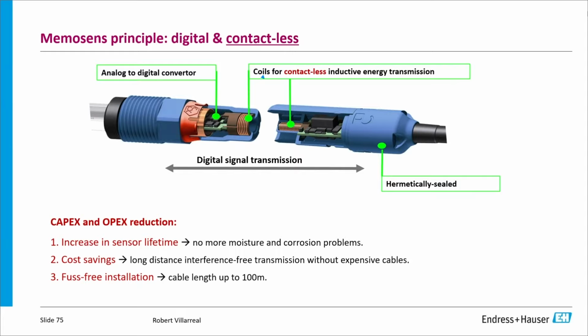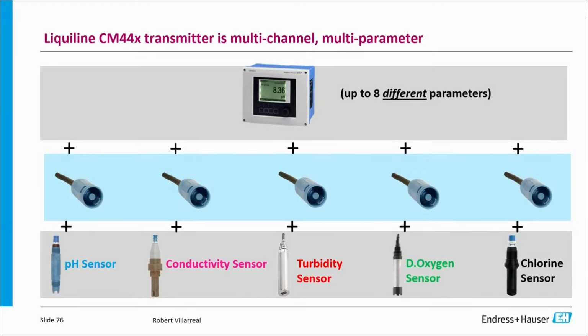All of the analog to digital conversion is done at the sensor itself instead of at the transmitter, and we only transmit that digital signal back up to the transmitter. We store all the sensor information at the sensor, so you can calibrate probes, something like a pH probe, offline in a lab or benchtop setting. Then whenever you need to calibrate one in the field, you simply swap it out and that calibration curve jumps all the way up to the transmitter level. It uploads automatically and recognizes it when you plug it in, which saves on a lot of maintenance and lifetime issues in the field.